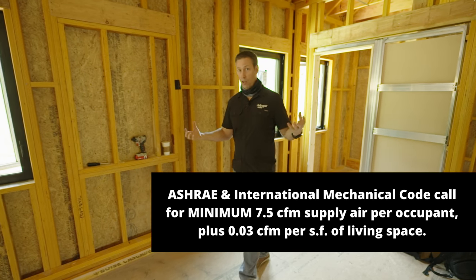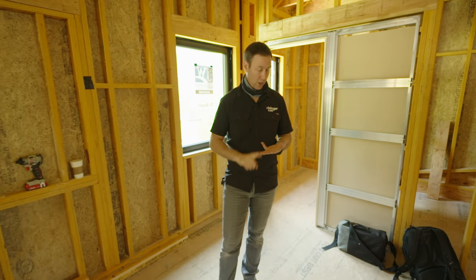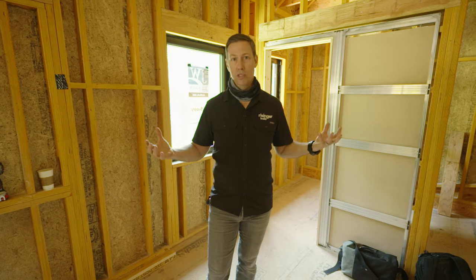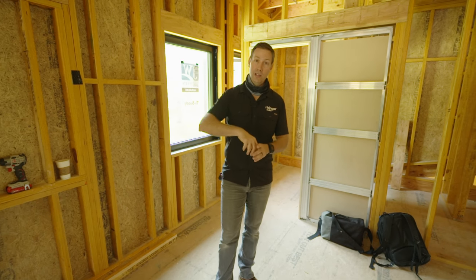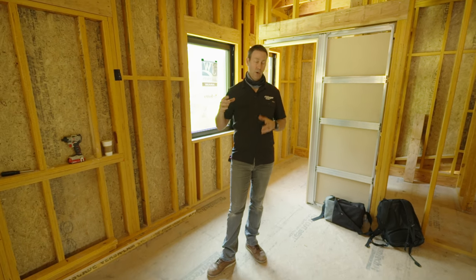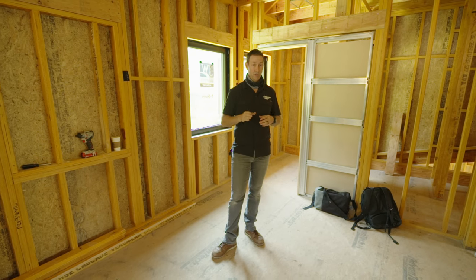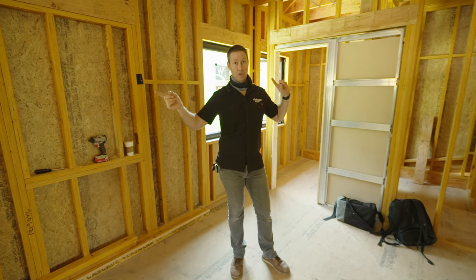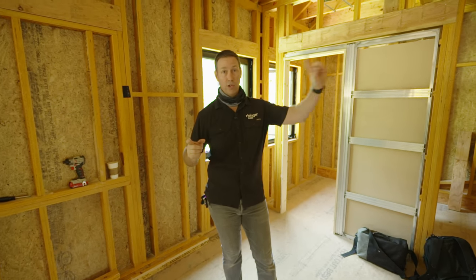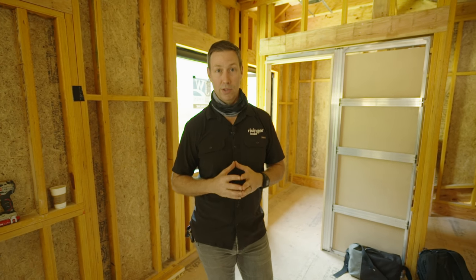Basically every area of my house where there's a bedroom or a public area is going to have one of those, a place to bring fresh air in. And then all the other places, bathrooms, laundry rooms, anything basically wet or stinky, that's going to have an exhaust out. What I love about this system is I just have two inputs: two 8-inch ducts, one coming in and one going out. And my ERV upstairs is a balanced system.